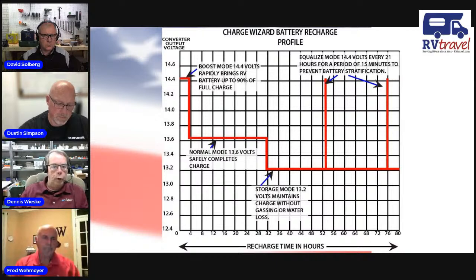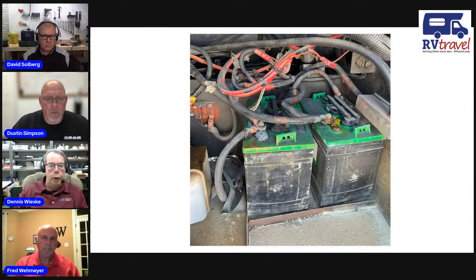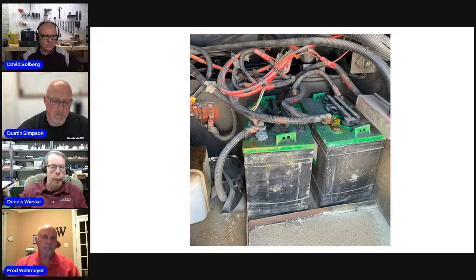Now, the batteries that Dave just showed us a minute ago, they were neglected. Unfortunately with the charger, if you have a dead battery, a bad battery, a shorted cell, the Charge Wizard, before you plug it in, is actually analyzing the voltage coming back from the battery. If that battery voltage drops below a preset voltage, in our case below 11.9 volts, it's going to go into boost mode as soon as you plug in your shore line.